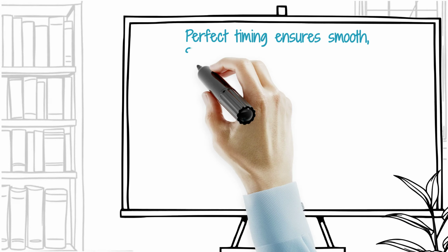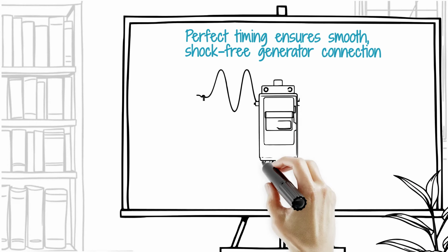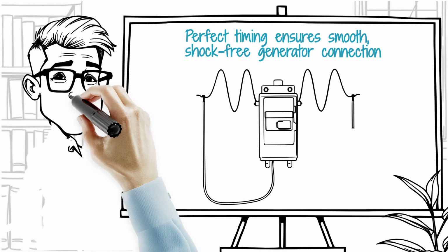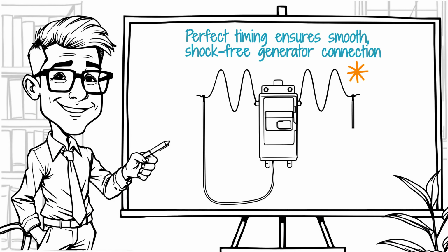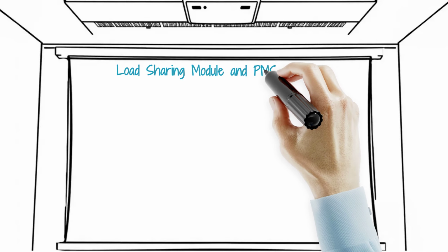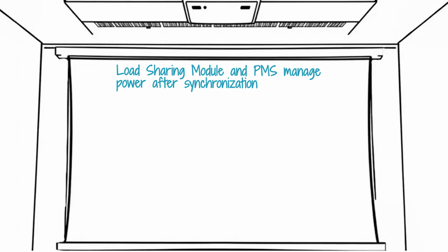If the timing is perfect, the circuit breaker closes at the exact instant the two electrical waves align perfectly, resulting in a smooth, shock-free connection. Once paralleled, the automatic synchronizer hands control over to the load-sharing module within the power management system, or PMS.